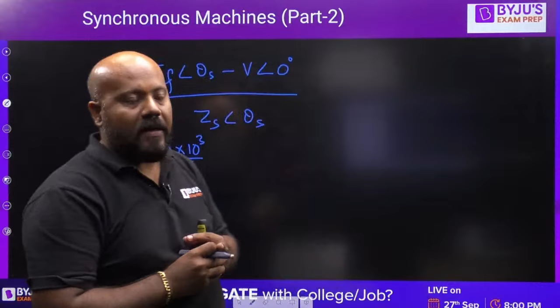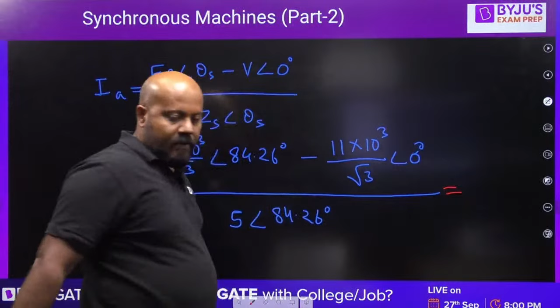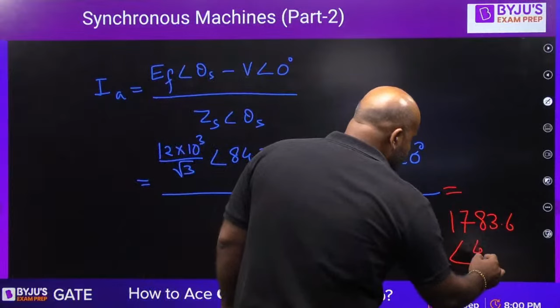The angle you have just found, it is going to be 84.26 minus, it is going to be 11 kilovolt, angle 0 degree, divided by ZS given as 5, angle 84.26 degrees. Just find this value. As per my reference, you must be getting the current as 1783.6 and the angle you will be getting as 45.12 degrees amperes.